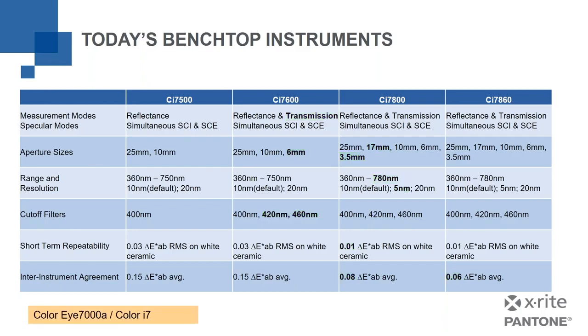So then let's take a look, excuse me, at how the 7000A and the Color i7 compare to these. And I'm going to just lay an orange thing over the top. So those two instruments do reflectance and transmission as well, but they don't do simultaneous specular included and specular excluded. So what that means, if I was using a 7000A, for example, and I need to measure both modes, I have to calibrate two different methods, and I literally have to measure my sample twice. So if I need to do that on a regular basis, that's a lot of extra time and work. Whereas with all of these instruments, the newer ones, it's simultaneous. It's calibrated for both. A single measurement captures both sets of data. That's a huge time save.